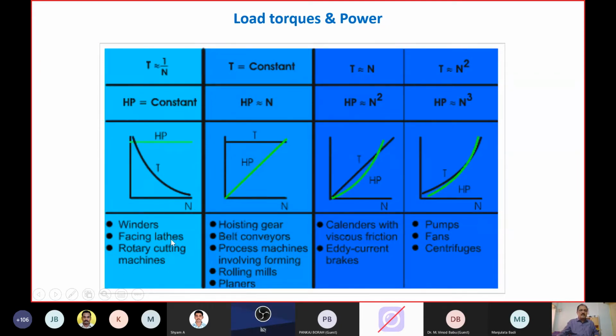Some of the applications are winders, rotary cutting machines, internal grinding machines, lathes and things like that. So as you increase the speed, as the component becomes well grooved, the HP or the kilowatt will remain constant, but the torque will reduce. So the motor should be capable of delivering the reduced torque. Similarly, torque is constant. These are applications like all our material handling and process machines, where the torque will remain constant throughout the change in speed. The power will increase in direct proportion to the change in speed. So these are applications which are largely used in industries, like we already discussed.